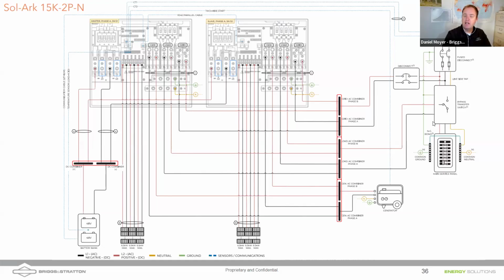Another piece of equipment: if we have a generator here and we want to power the Solarks, we have to combine the L1 and L2 of the generator in a load center and feed it up into the generator ports. Likewise, if we have batteries, we have to have a single combined battery bank that then flows up into both of the inverters. That's a lot of extra conduit, combiners, wire, and a bypass transfer switch that you're seeing on this slide.